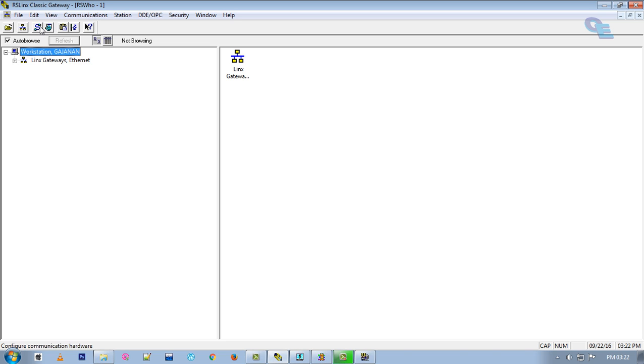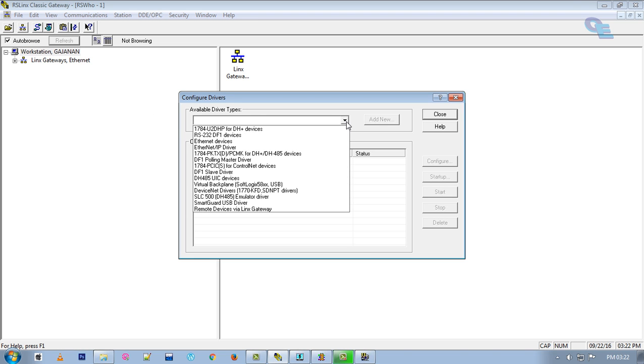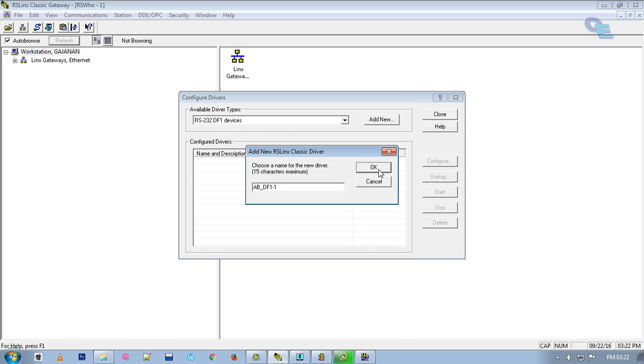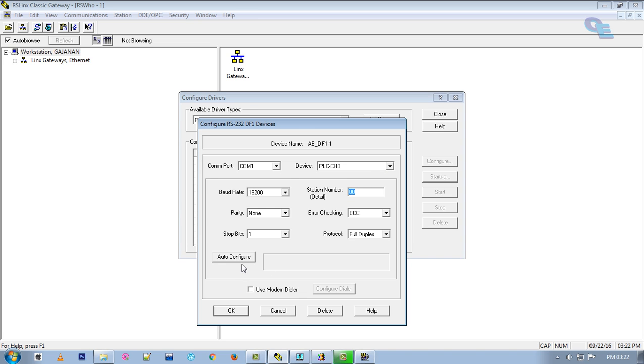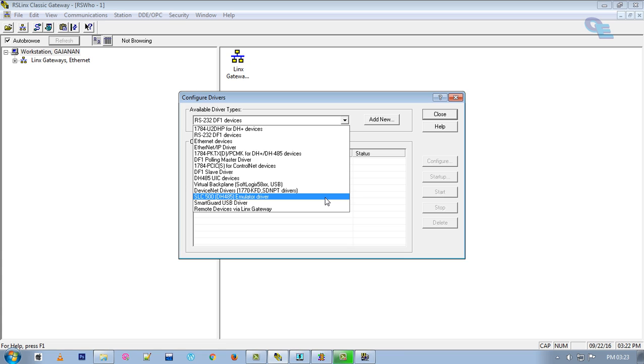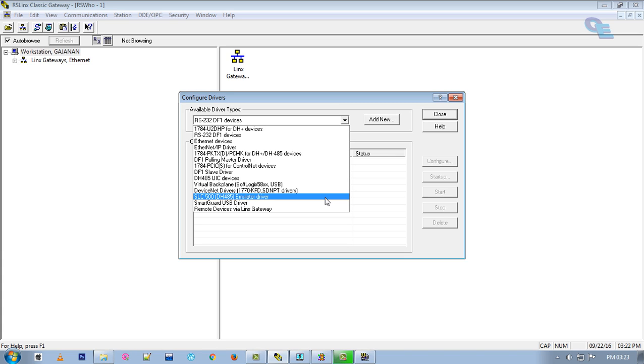For that purpose we have to create a driver. If you are connecting a PLC directly to the RS Linx software, you have to select the proper cable you are using. Suppose you are using RS 232 DF1 device — click Add New and click OK. If you have connected your PLC to the PC, just click Auto Configure and it will configure automatically, and your driver will be added.